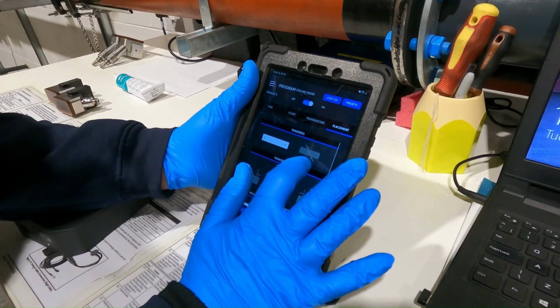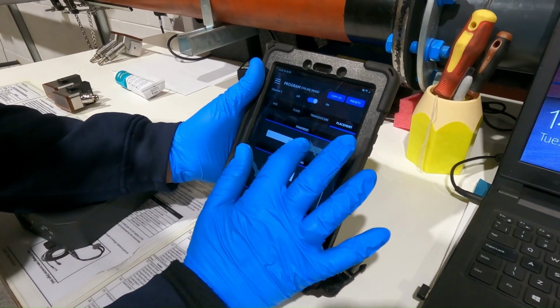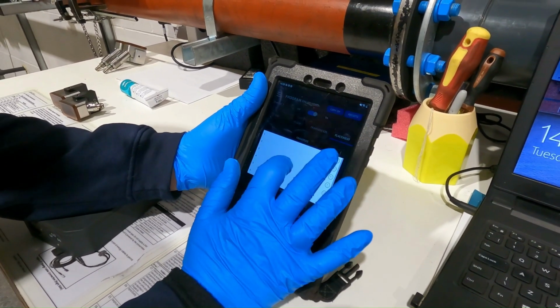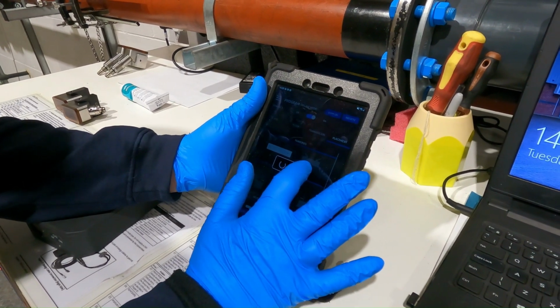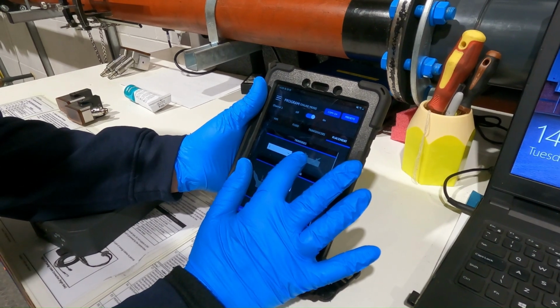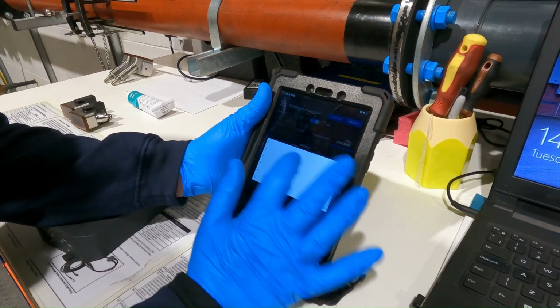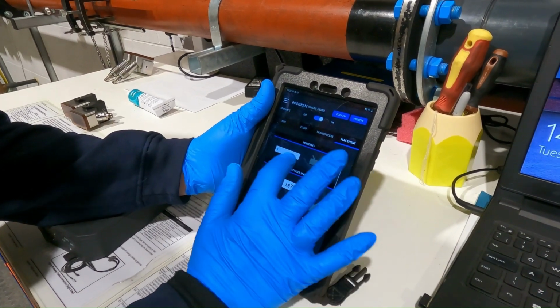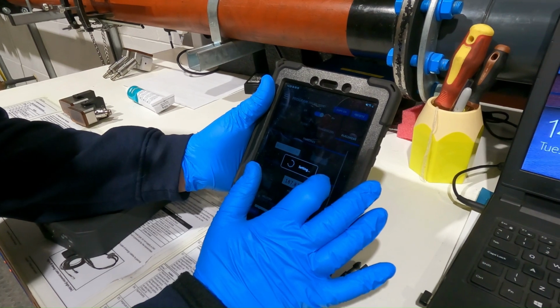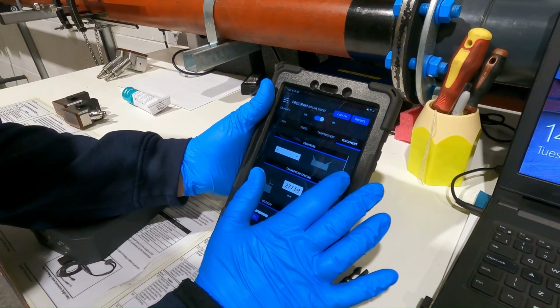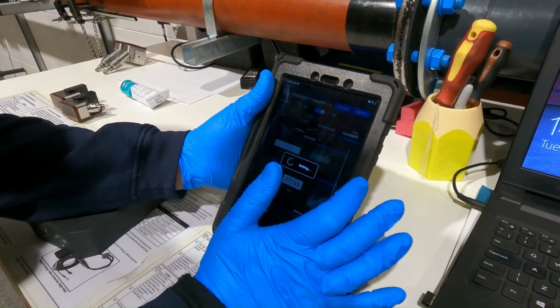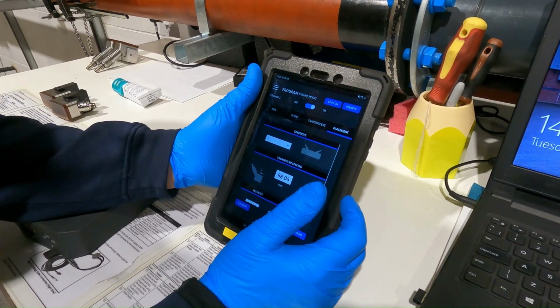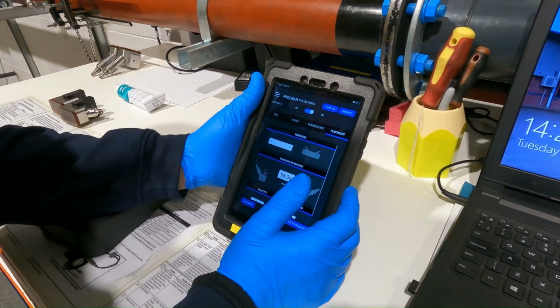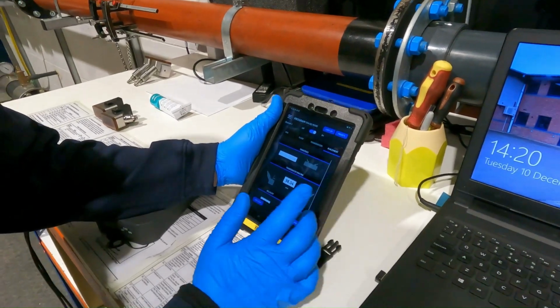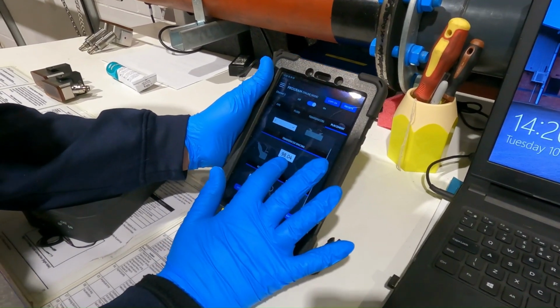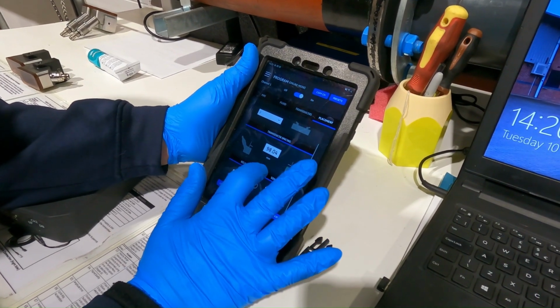If we pick one traverse, with all the odd numbers really, the one transducer is on the opposite side of the pipe to the other. Dual traverses, or reflect mode as some people call it, or the V, is where both transducers are on the same side. If you notice, I did the 4 or 6, that's how many times the signal reflects. Okay, so we're going to use 2 today. That's the go-to type if there's no problem, if it's not too big a pipe and not too difficult an application. Already it's given me a transducer spacing between the two of 98.04.